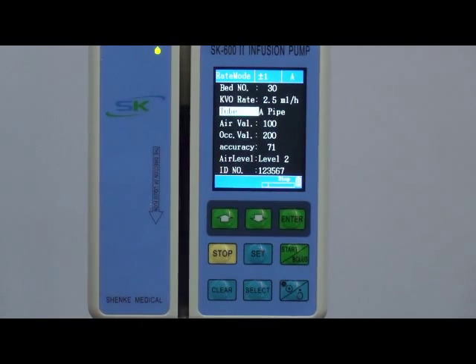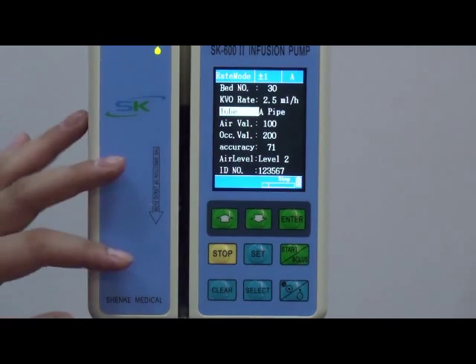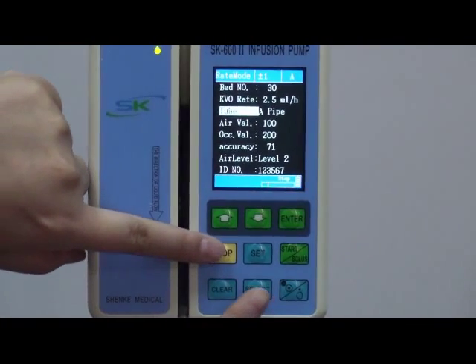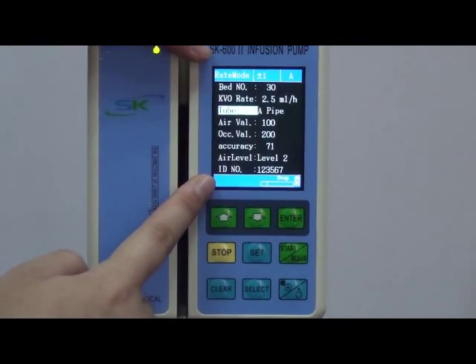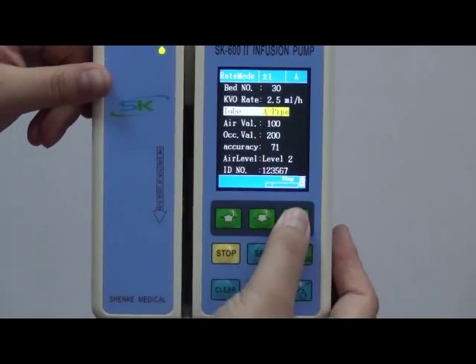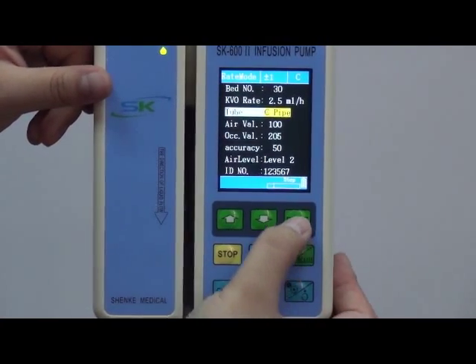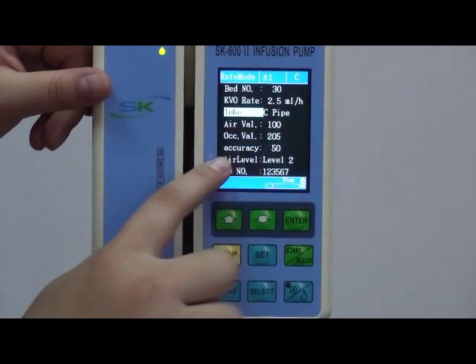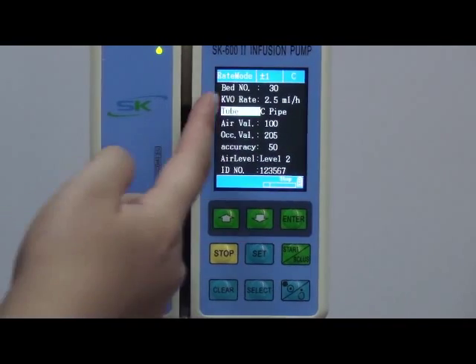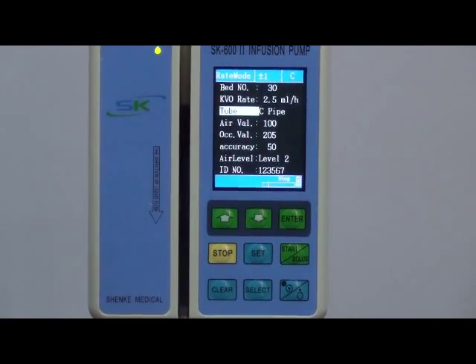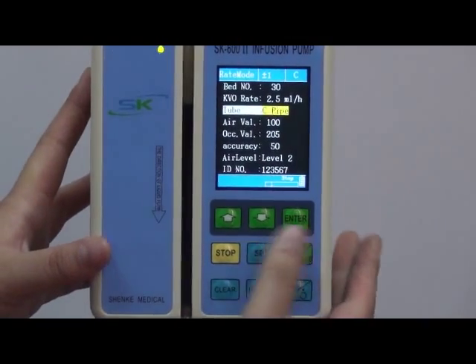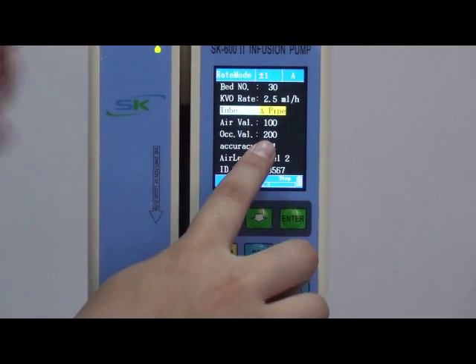Maybe at 3 p.m. she wants to use another brand IV set, pipe C, for the infusion pump. She again presses the start key, then presses stop and select keys together to enter into this interface, and then chooses tube. Press enter key, choose C. You can see the air value, occlusion value, and accuracy value all change. Now it's suitable for pipe C. Then the nurse could just use pipe C for the infusion. Okay, now I want to change it to pipe A because this is the default value, and we just think the hospital uses pipe A the most.